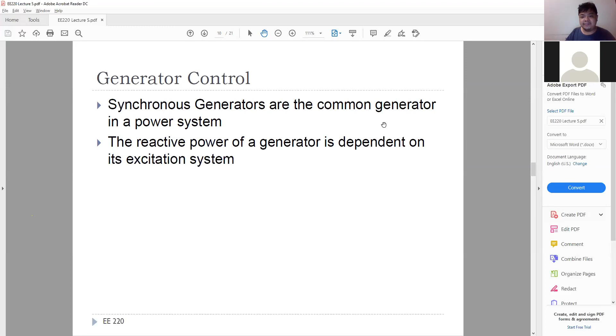Generator exciter can be quickly modified for voltage regulation. However, MVAR production of a generator depends on its capability and availability. So there's what we call an MVAR capability curve for generators.